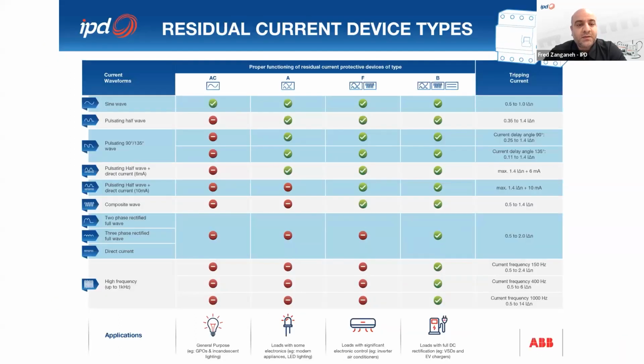Great information. So Ian, we have a number of types of RCDs available. Can you please run through the differences? Sure thing, Fred. There's quite a number of them, and they all have different characteristics. When we're looking at this table, we have to remember that most importantly, we're talking about the wave shape of the earth fault. We're not talking about the supply mains to the RCD. People can get hung up on that a little bit as we get into the higher spec devices, which we'll talk about in a moment.